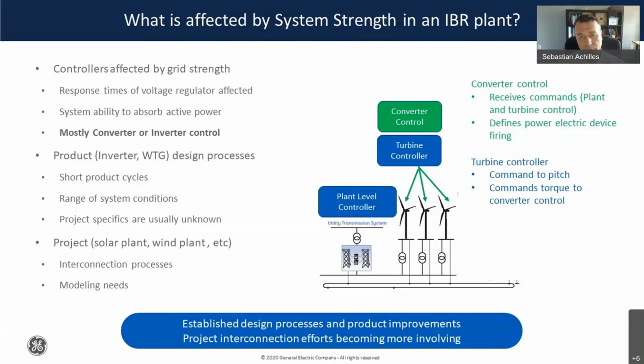It will try to respond to meet those commands, for example torque and reactive power, but during a fault it may depart from those commands in order to meet a particular performance requirement. The output of this converter control, which could be a converter plus an additional card, would define the firing of the electronic devices. So this is the most affected controller.